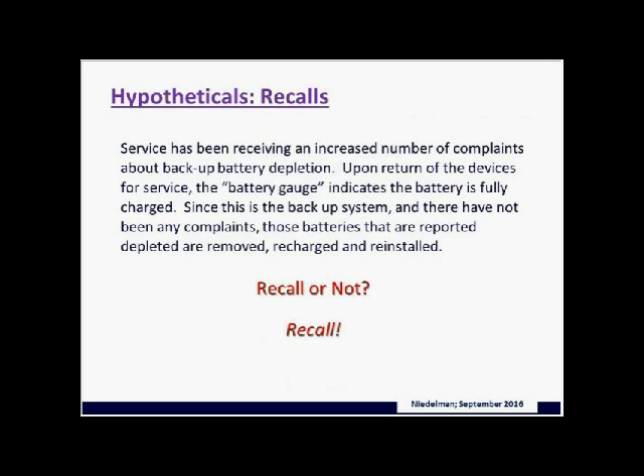Another one: services are receiving an increased number of complaints about battery backup depletion. Upon return of the devices, the battery gauge indicates the battery is fully charged, sort of like your gas gauge on your car. Since this is a backup system and there have not been any complaints, those batteries that are reported depleted are removed, recharged, and reinstalled. So it's a false sense of security that you think you have battery backup and you don't. Is that a recall or not? Even though it's a backup system, it is a recall. That is certainly an indication that's of concern.